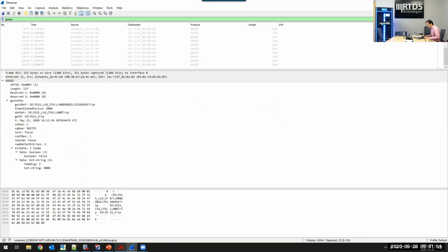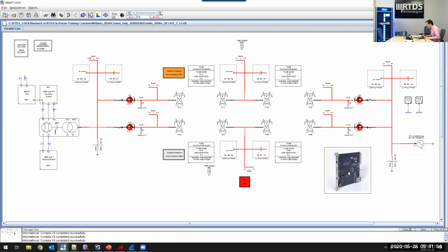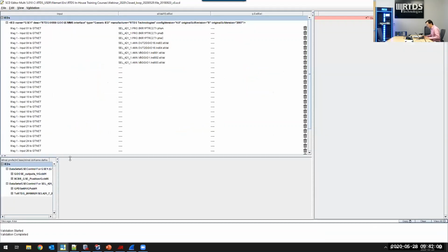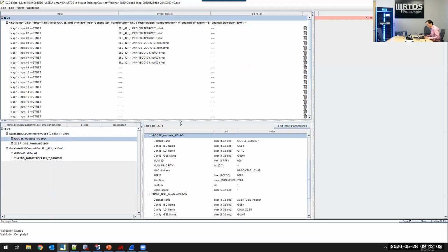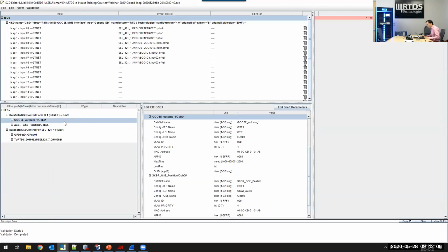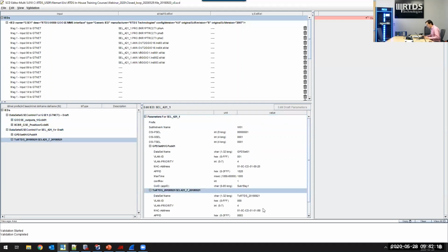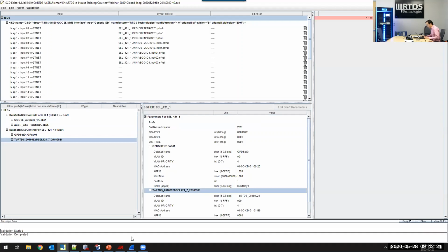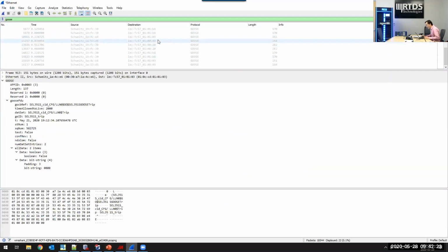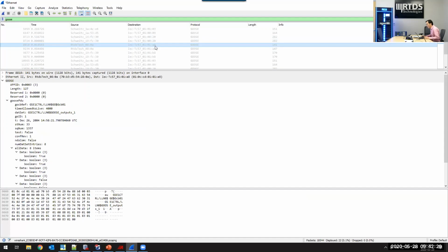Let's stop here, and let's double check the destination MAC addresses for the GTNet and also for the relay. So the GTNet sends the Goose messages to the address of 010188, and the SEL relay is sending the Goose to 0101B8. If we go back to Wireshark and find the 010188, that's from the GTNet. Let's do a filter here.